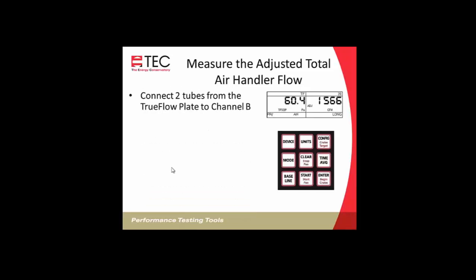Next step, we'll measure the adjusted total flow. So we've installed the TrueFlow plate. We've already taken the normal system operating pressure and entered it in the gauge. We'll connect the 2 tubes from the TrueFlow plate to channel B. There are colored tubing on that, but where you connect the tubing, you'll get the same measurement whether you put a tube on input or reference. So you'll connect those 2 tubes, one to input, one to reference, the 2 tubes coming from the TrueFlow plate. We'll change the device to TF for TrueFlow. So we'll push the device button on the DG700 gauge, and we'll keep pushing that to toggle across the different devices till we get to TrueFlow. And then we'll change our configuration to match the plate being used. The default will be 14, and if we're using the 20, we'll hit the config button and toggle to 20.